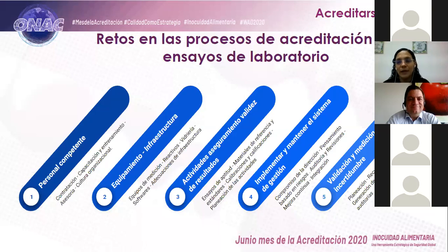Also, calibration and assessment, and qualification, have to be done with competent suppliers, and the staff in charge knows who the vendor is. In this case, it has to be an accredited vendor in terms of the calibration procedures, and that needs to be scheduled as well. You need to do planning of the time in the lab, because this has to go along with the services and the customer service, but everything needs to be combined.